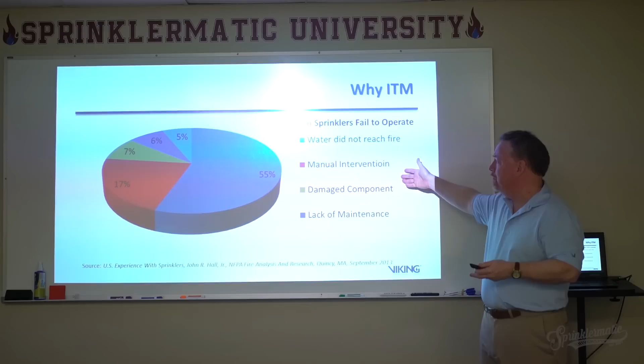Manual intervention accounts for another 17% of the time — that's somebody closing the valve after the fact, after the fire's already started. That may be a mistake, or somebody not understanding what that valve was controlling, or thinking the fire was out. Anyway, we've got some real issues here, but this adds up to about 72% of the time you're looking at simply a closed valve.